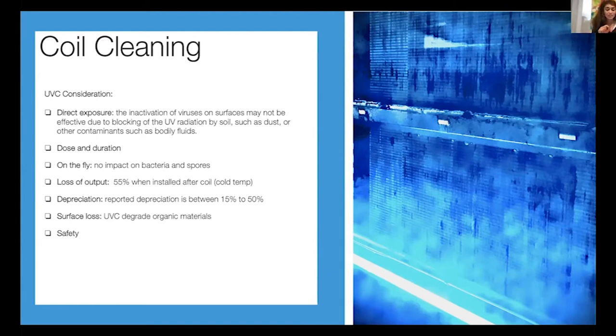So actually for UV, and this is very different from electronic air cleaners, we have an ASHRAE standard and ASHRAE guideline. We know UV in principle works, but you need to make sure that the intensity, so the dose and duration, are correct for your application. Like if you put the UV behind the cooling coil where it's cold, the lamp intensity output can be lost by 55%. So it's very important, whether you're putting it before the filter, before the coil, after the coil, or basically in the room, to know how much duration of exposure. You need to get this from the manufacturer, have an engineer take a look at it and spec it correctly.